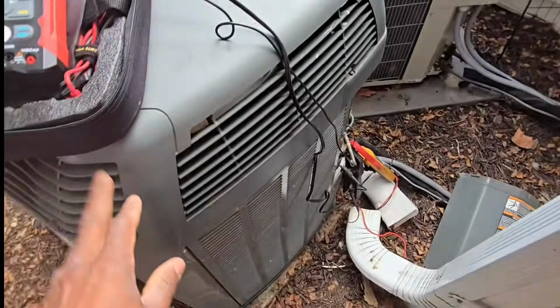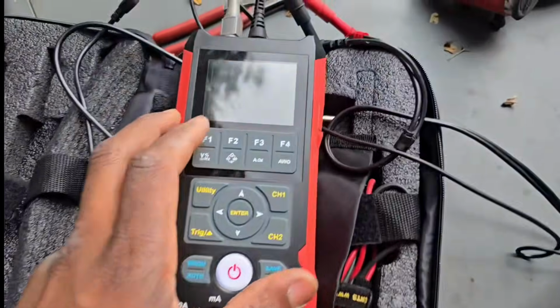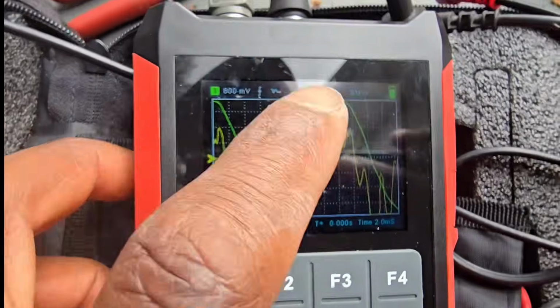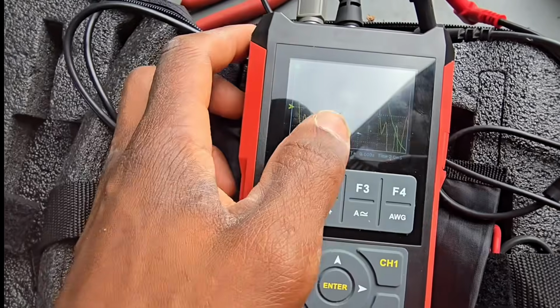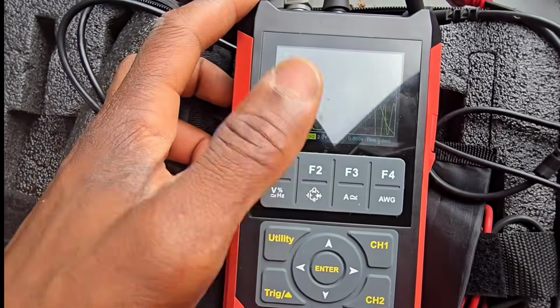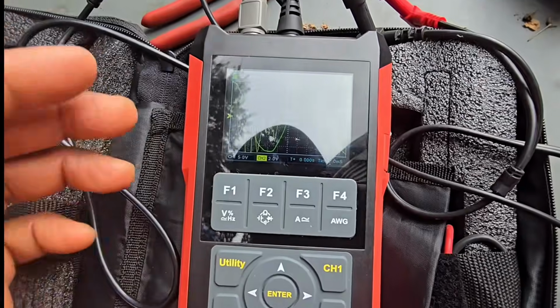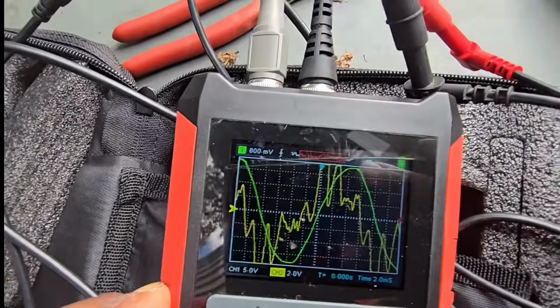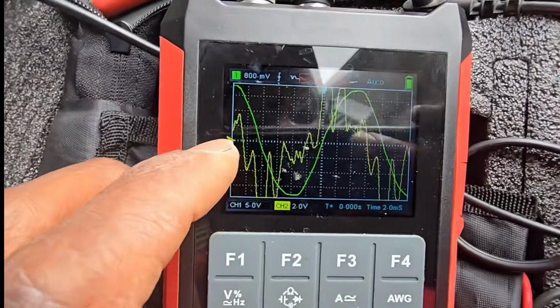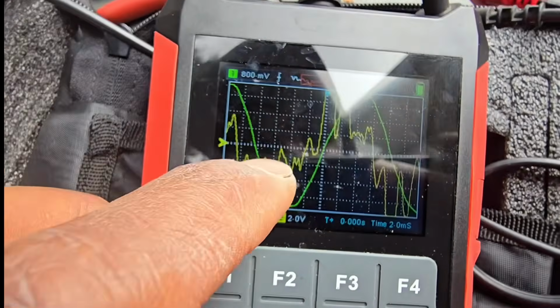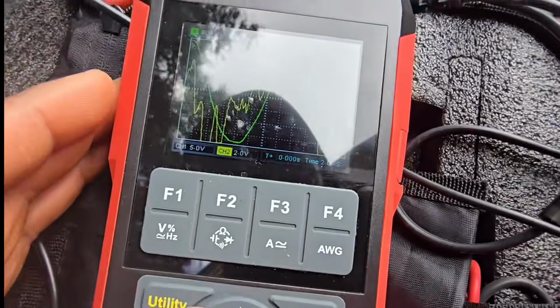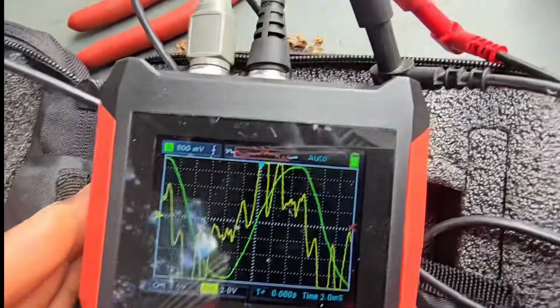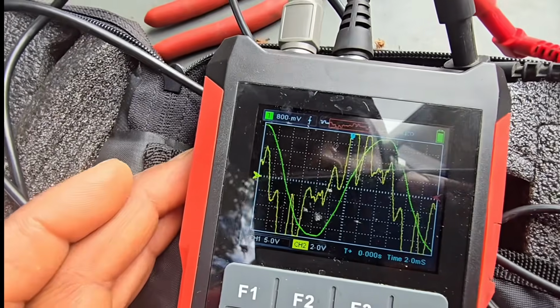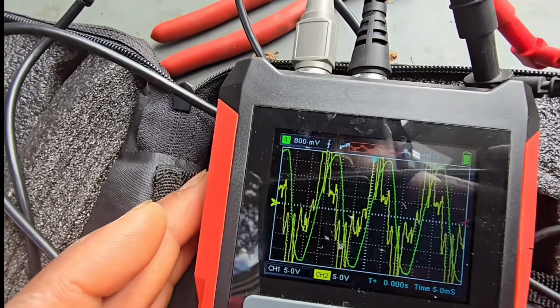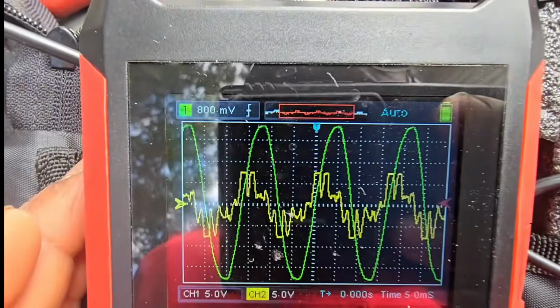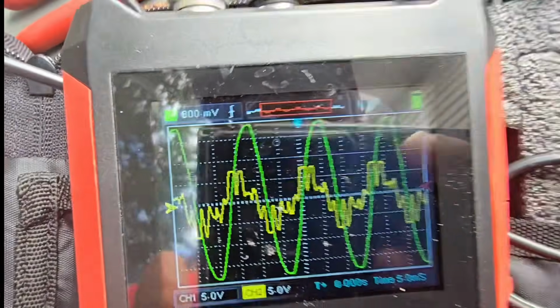Okay, so I've got this set up on a unit. It's an older Trane R22 system. As you can see, the yellow line here is your current, green line is voltage. I've got it set on basically only one leg of power, so it's only reading 120 volts between ground and line voltage. But as you can see, this amperage sine wave is very distorted, very messy looking. That right there is just an indication of poor power quality on your current. It's just not a very nice looking sine wave.